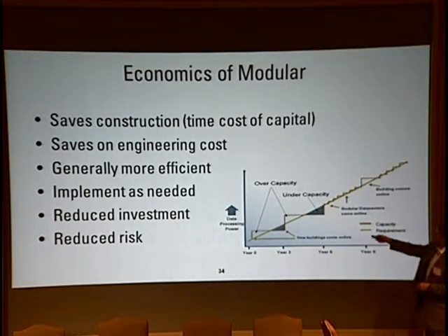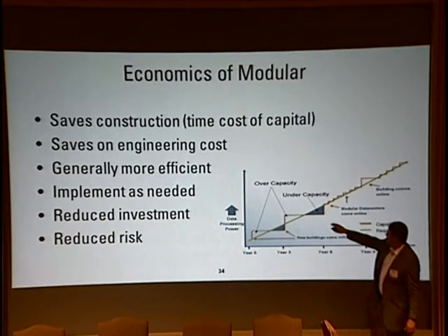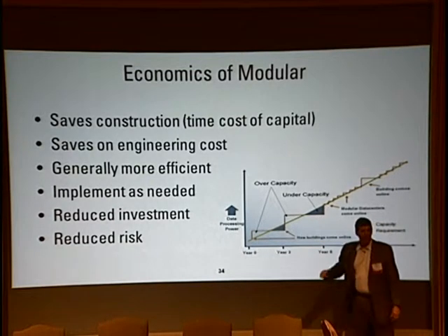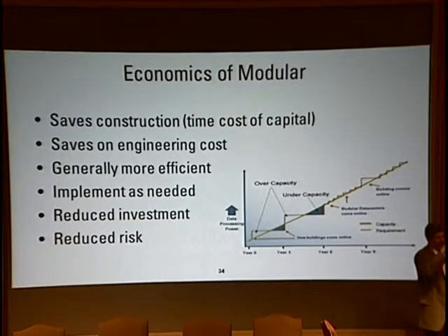If the green line is your anticipated load, you have to keep that orange line above it all the time. So you're going to make big chunks of capacity if you're buying data centers. If you're going modular, you can make smaller chunks. And down even at the container level, these are a couple hundreds of thousands of dollars decisions that can go with your capacity.